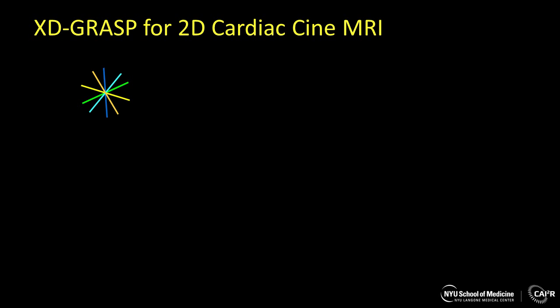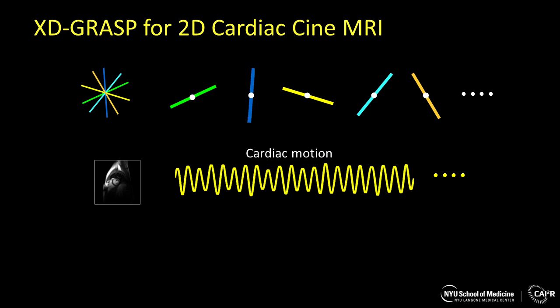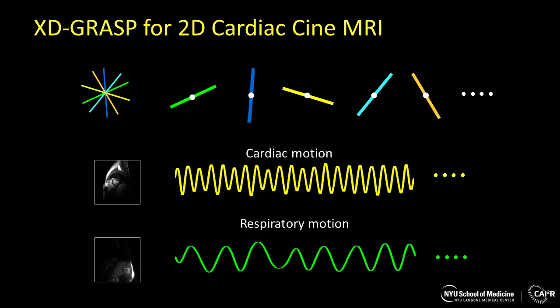In the next application, let's see XD-GRASP for 2D cardiac cine MRI. Here, we are using a 2D golden angle radial sampling, and we can detect the motion signal from the center of k-space. Based on the fact that we are using multiple coils for data acquisition and the frequencies of cardiac motion and respiratory motion are different, we can detect the cardiac motion from a coil element that is close to the heart, and detect the respiratory motion from a coil element that is close to the diaphragm.